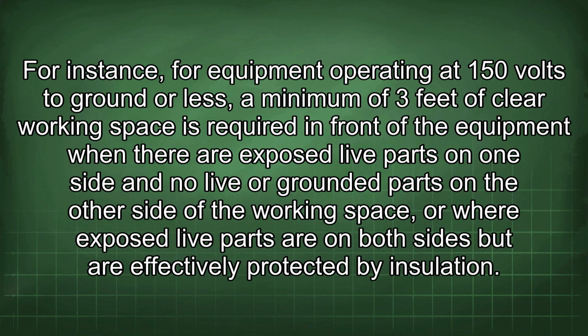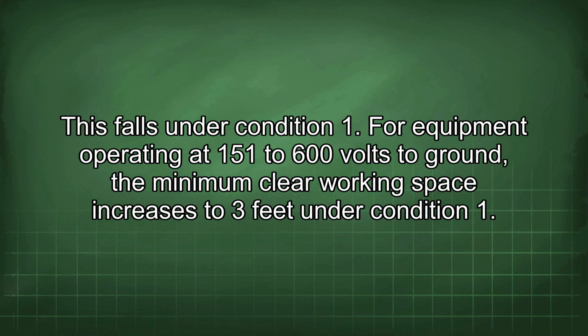For instance, for equipment operating at 150 volts to ground or less, a minimum of 3 feet of clear working space is required in front of the equipment when there are exposed live parts on one side and no live or grounded parts on the other side of the working space, or where exposed live parts are on both sides but are effectively protected by insulation. This falls under Condition 1.